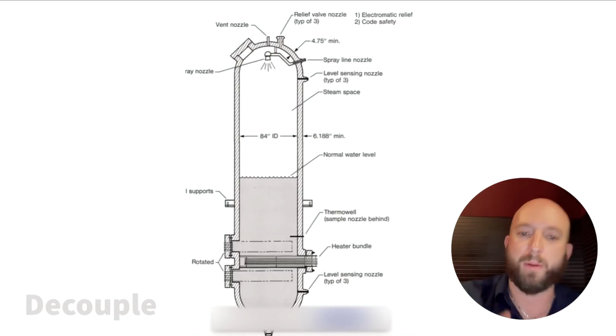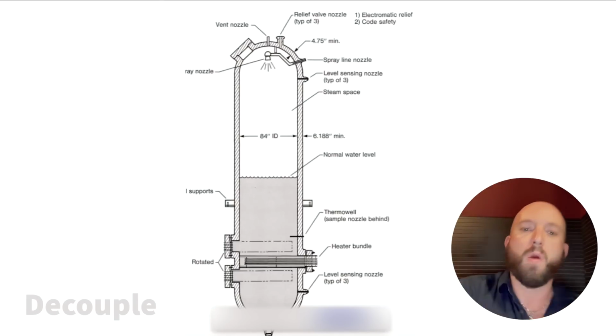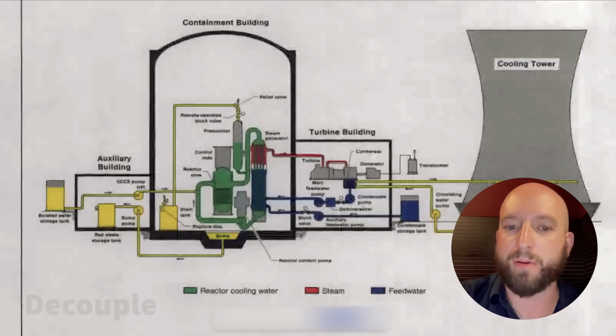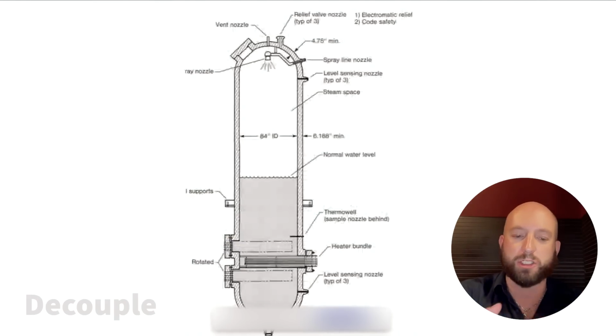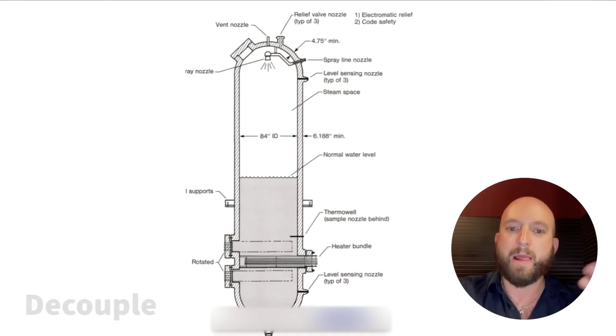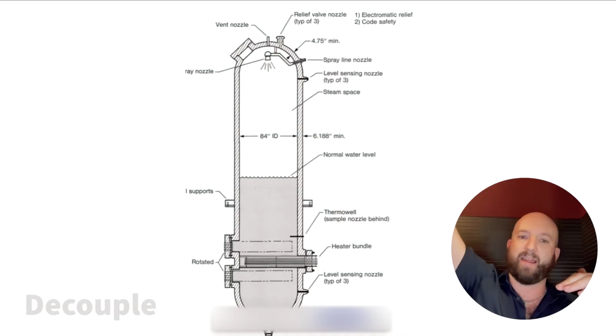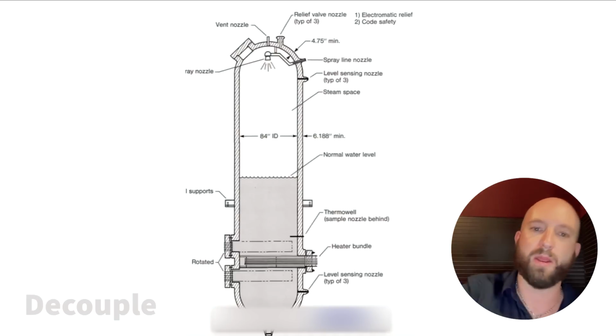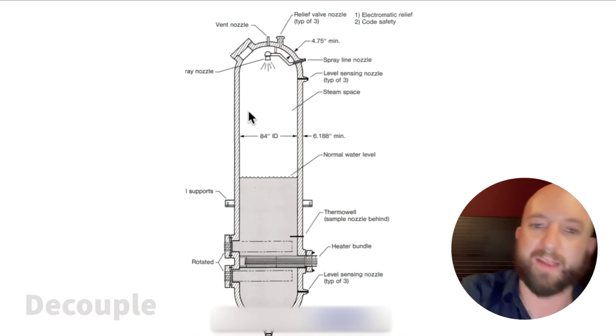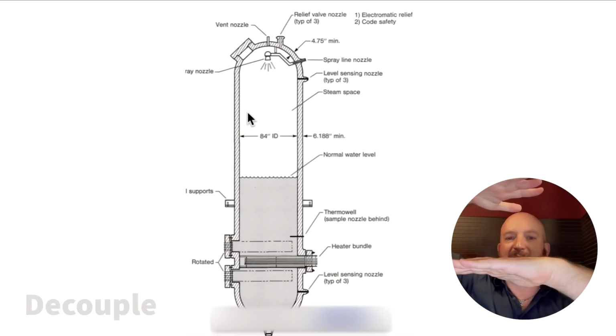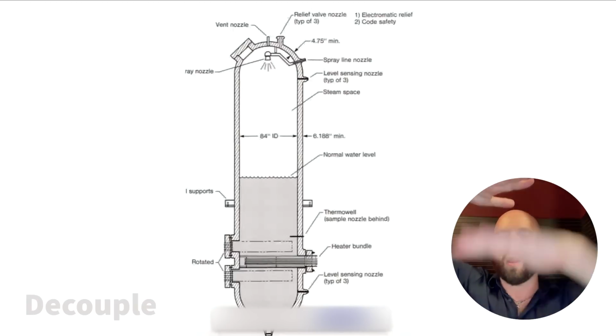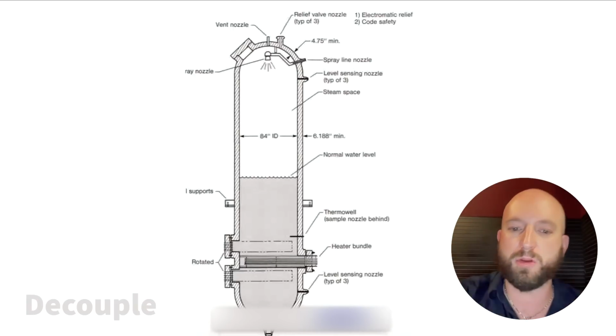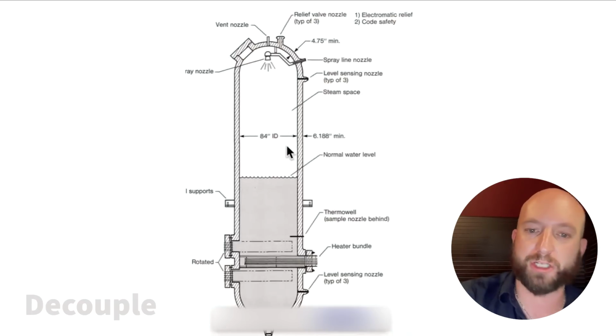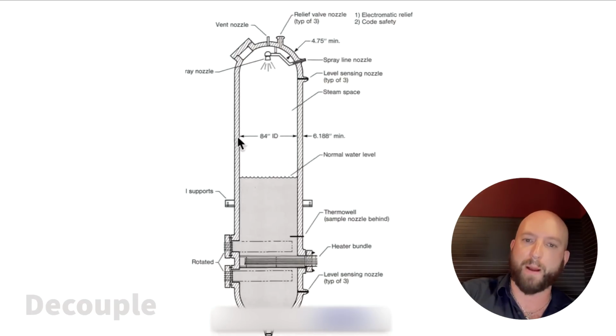This steam bubble acts like a piston. Basically, water is incompressible, which means that when we change the volume of water, you can have dramatic increases in the pressure of the system. What this steam bubble does is allow us to control the pressure of the reactor coolant system. And how do we do that? If we want to increase the pressure, we basically make the steam bubble bigger.